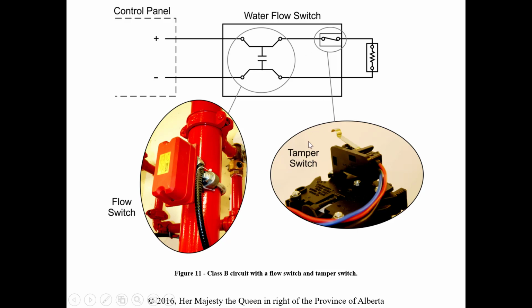So a lot of these devices have tamper switches. If you remove the cover, it opens this circuit. As soon as that's open, now we have an open circuit, it's going to go into a trouble scenario. It's not going to alarm, but it's going to go into a trouble because we have a break in our circuit. So we're not going to be going through the end-of-line resistor.